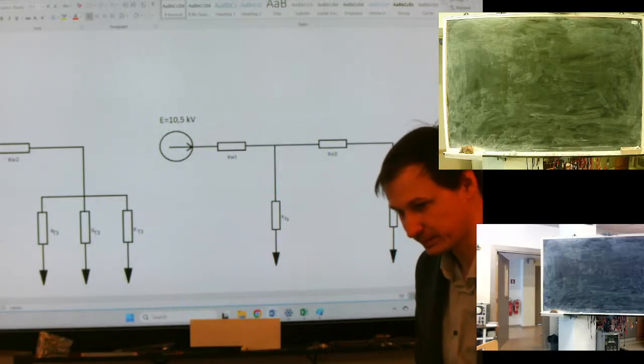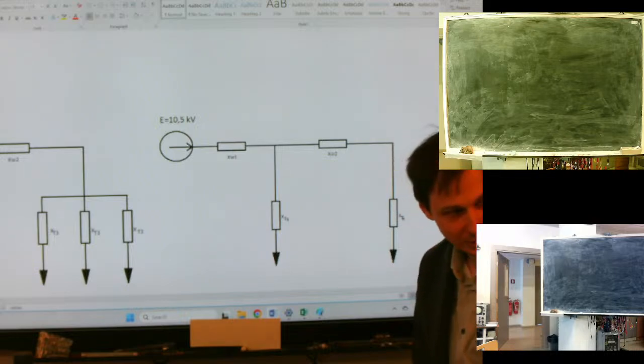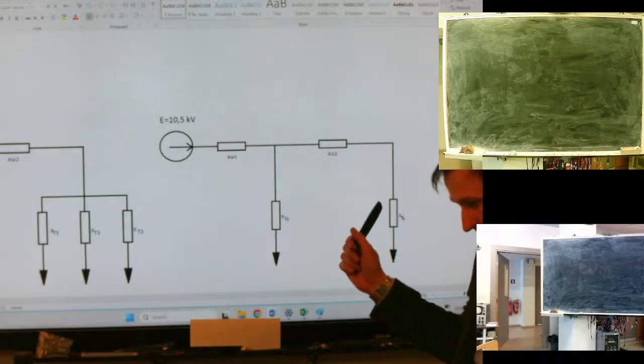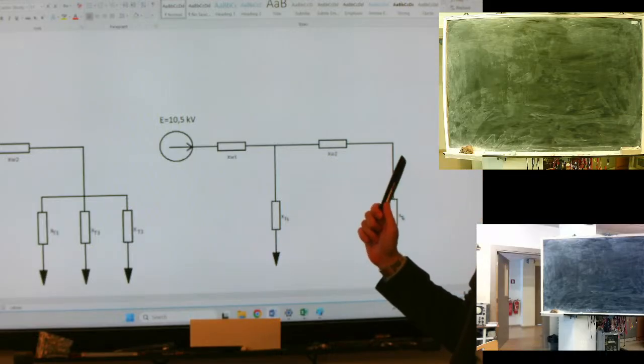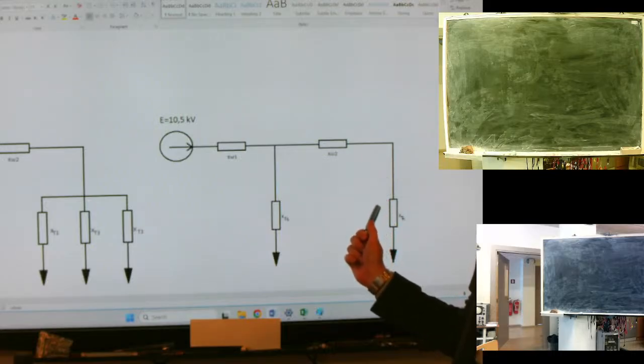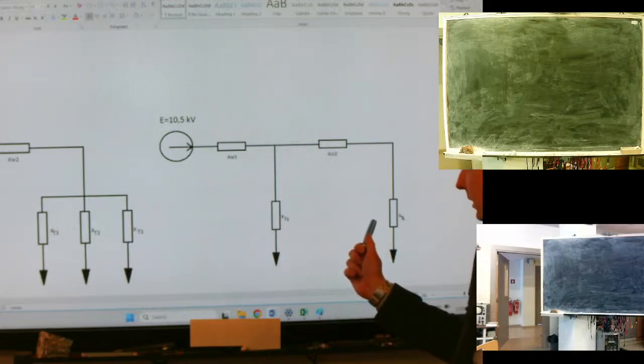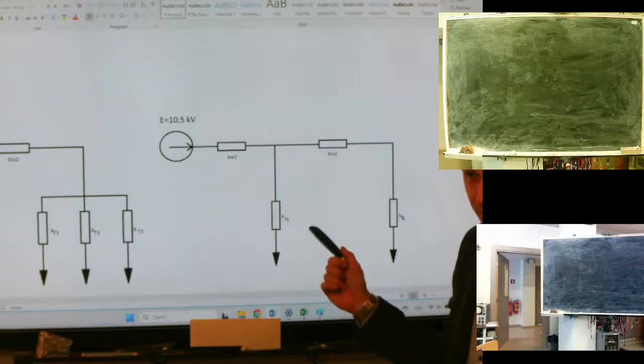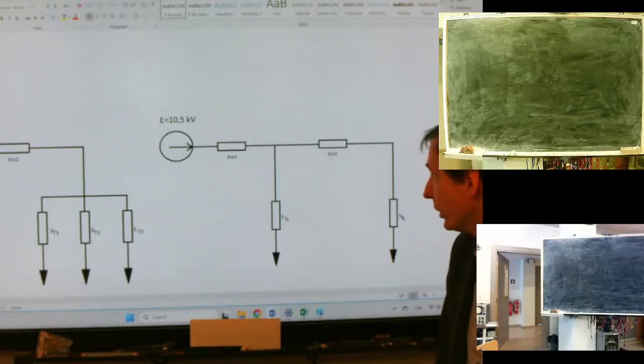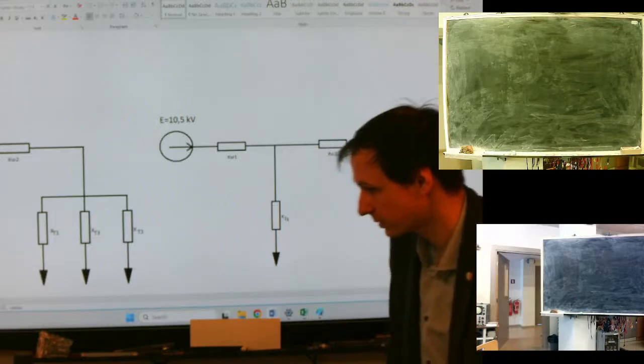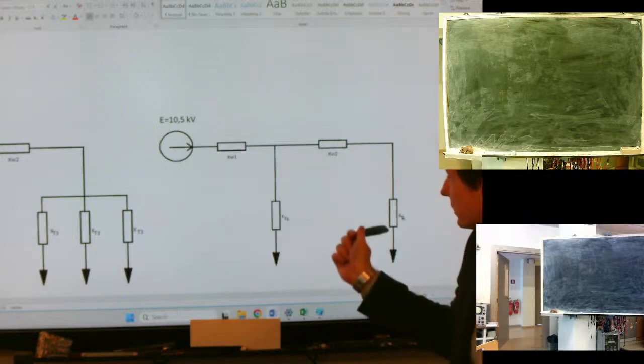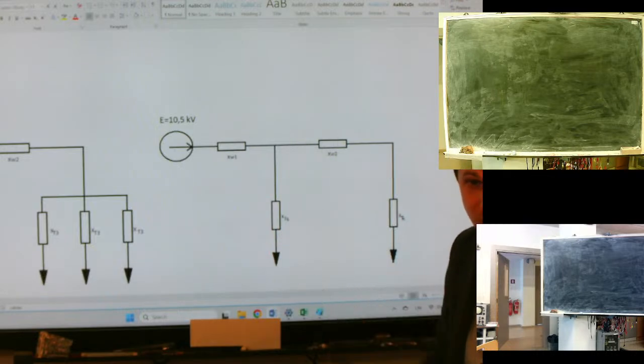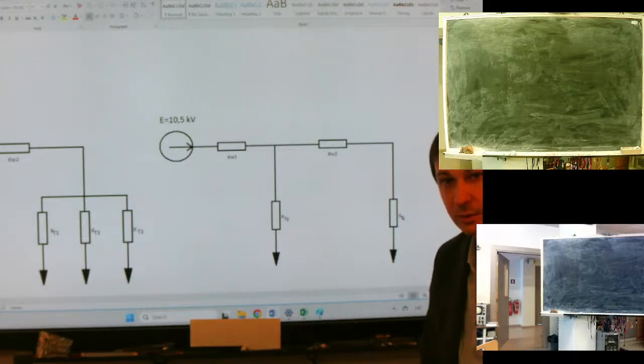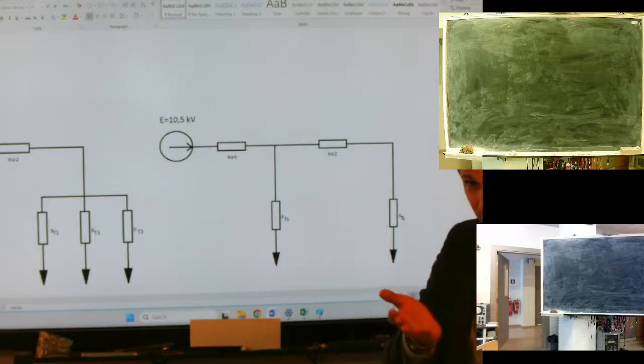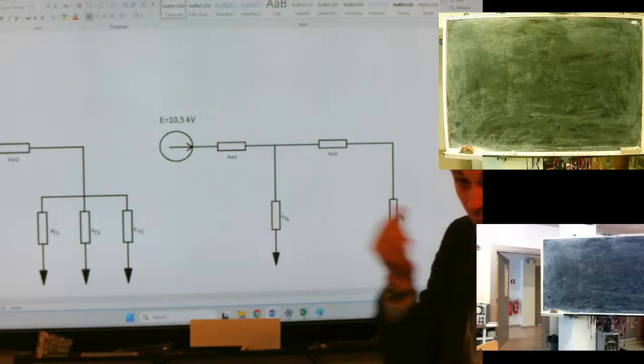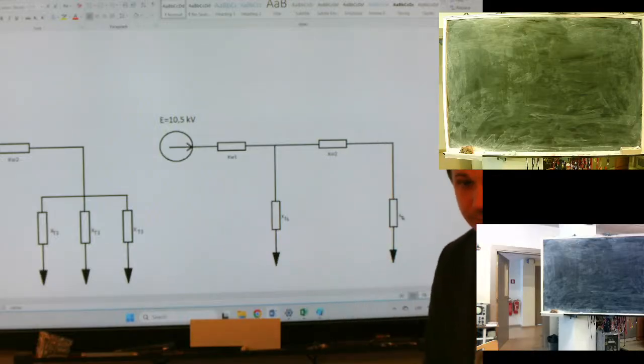Yes, that is why we are not saying that the fault location must be in place of transformer number 3. We say in a way of greater impedance. How could we know where is this? We need to calculate. So we need to calculate this branch, and we need to calculate this branch as well. And then we could compare. And choose, as you said, because your logic is right, yes, the lowest fault current value to check.